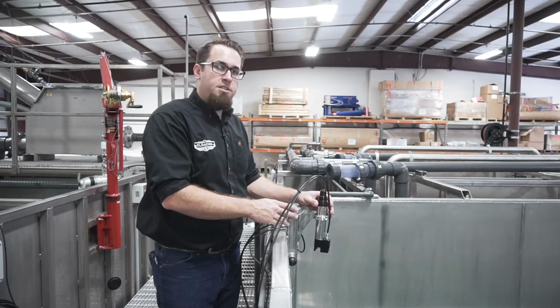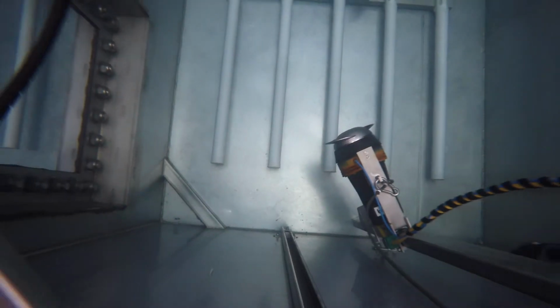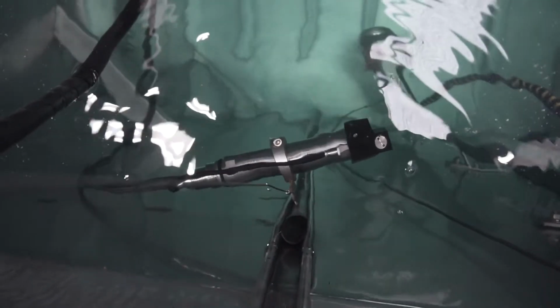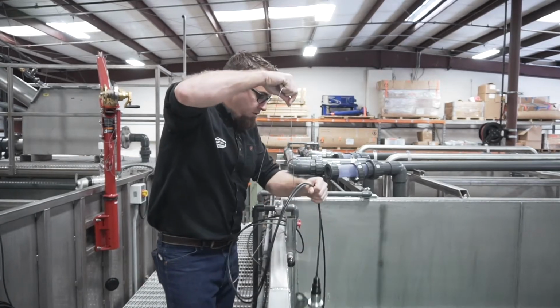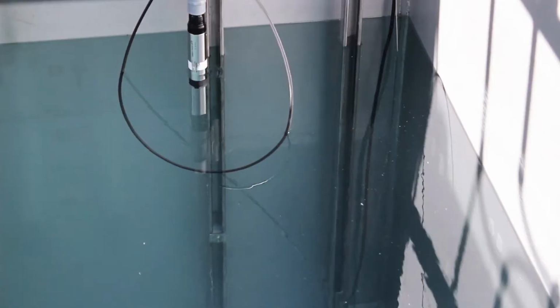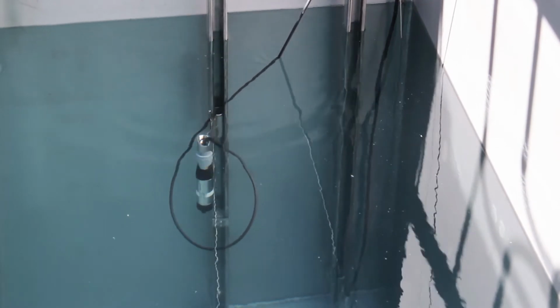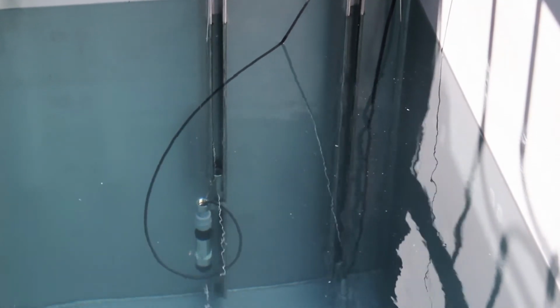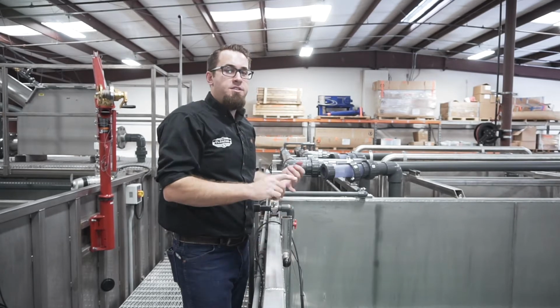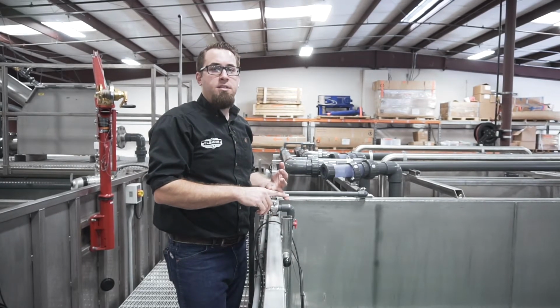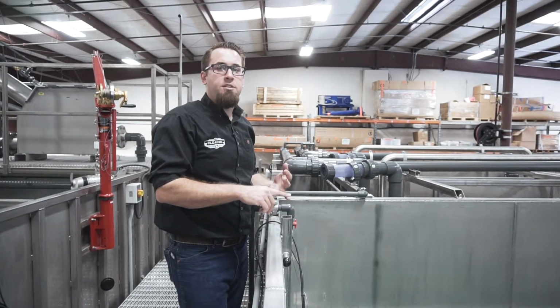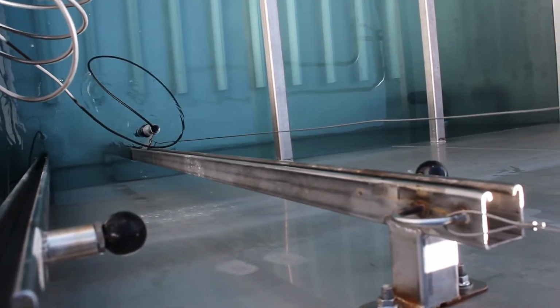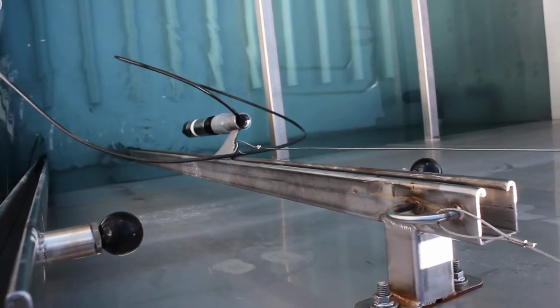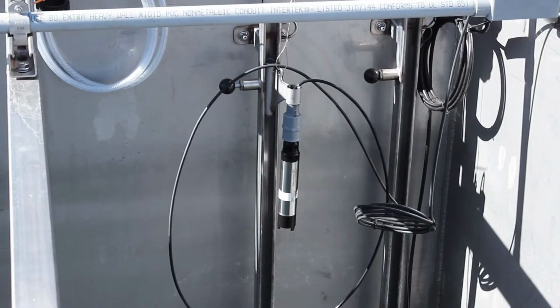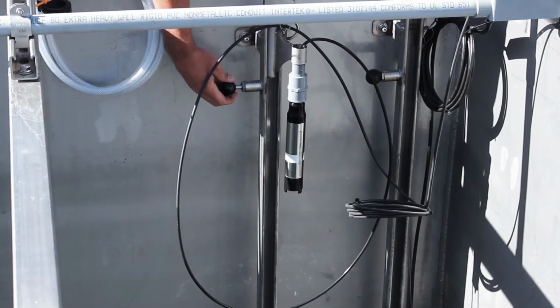The Cloacina slide rail system is something that we developed decades ago, and it allows for all of our sensory equipment to be mounted onto these so that you can easily raise up and lower down the individual pieces of sensory equipment into their specific strata that we designed them to be in the actual tanks. As a result, it reduces damage to the equipment. It allows us to put things in the specific location that we want to every single time. Additionally, it also avoids damage to the equipment by fixing it to a specific location rather than allowing the pieces of equipment to jostle around against the wall in aerobic conditions especially.